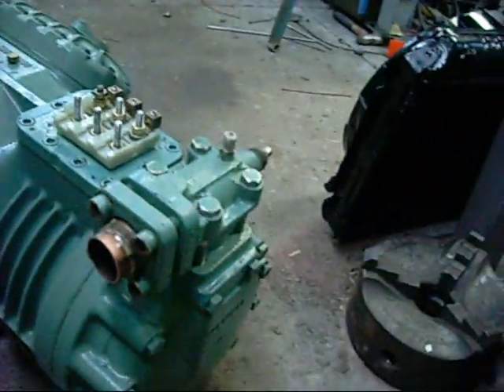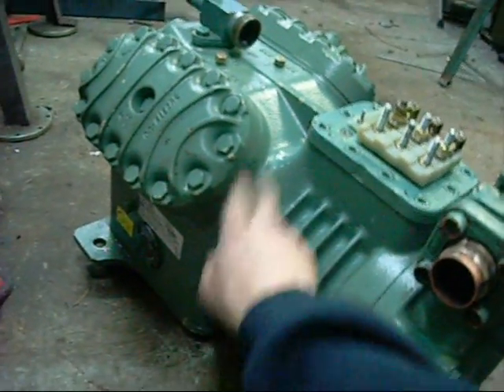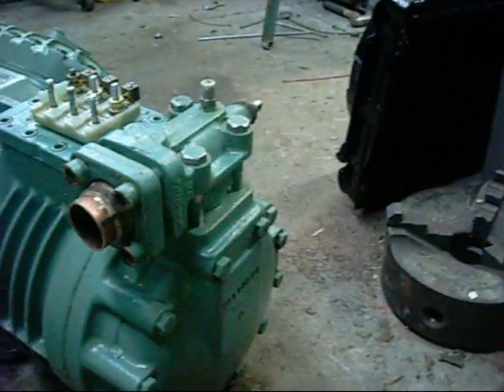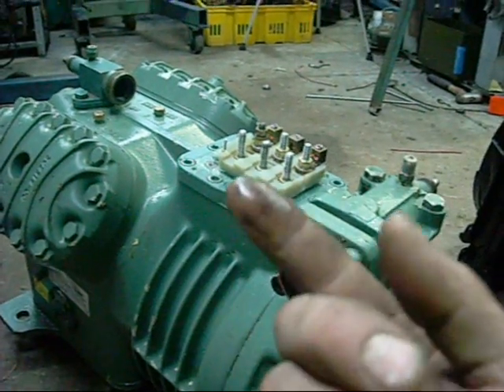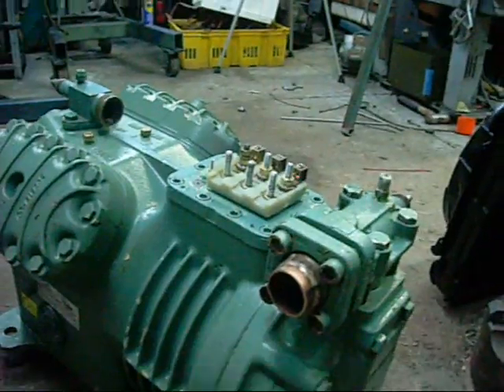King valves are still shut. I don't know what's in it, I don't know how it failed. It's still got a bit of oil in it. I've just given it a quick wash because it was rather manky. It came out of a supermarket cool room — well, chiller pump room or whatever you call it. I don't know why it failed. There's a bit of black residue in the discharge line, but I notice a lot of old compressors get that anyway from wear and tear.